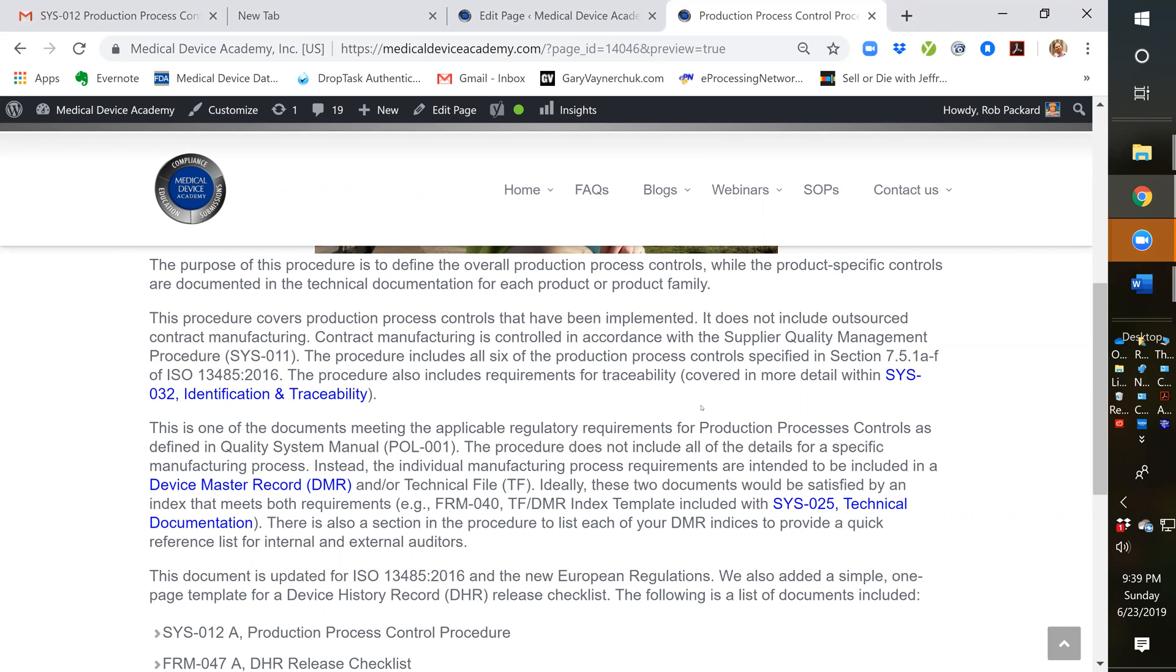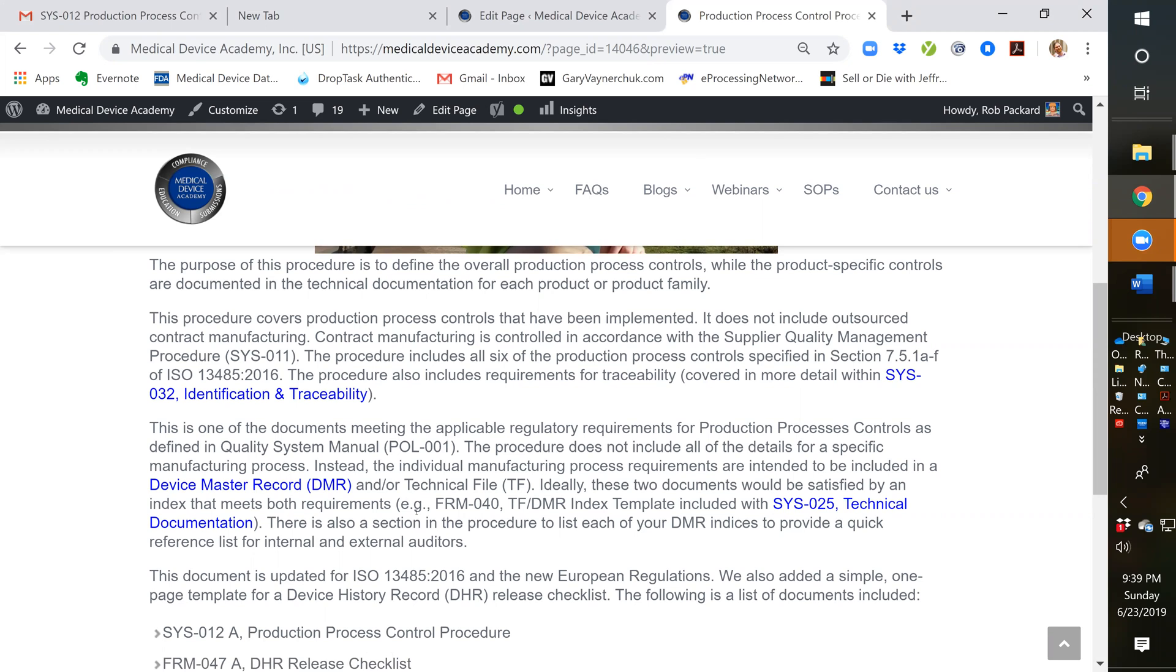Our identification traceability procedure is SYS-032. In addition, we include requirements for device master records or DMRs. We also include a checklist for release of each DHR or device history record for each batch or lot or serial number. We also have reference to UDI requirements. And we include basic things like process validation, traceability to equipment, traceability to calibration devices, and line clearance activities.